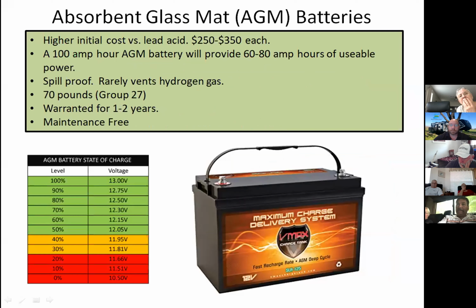On an absorbent glass mat battery, it costs quite a bit more. They're about $250 to $350 each. I've seen some lately on Amazon, which run right around $200 to $225. A 100 amp hour AGM battery is going to give you 60 to 80 amp hours of usable power, so quite a bit more than your lead acid. They are spill-proof. Now, they say that they don't vent hydrogen gas, but if you ran into an overcharging condition, which rarely happens, you could wind up venting some hydrogen gas. So I would still recommend that you keep these batteries vented.